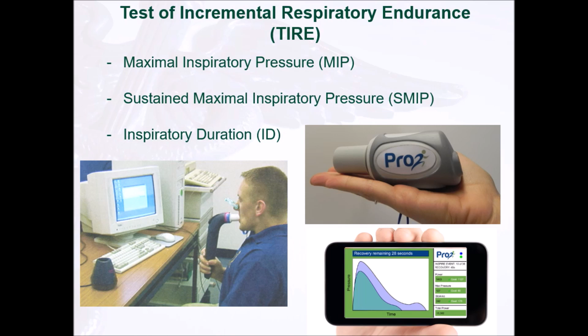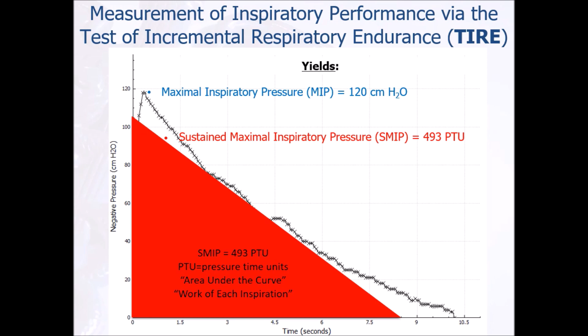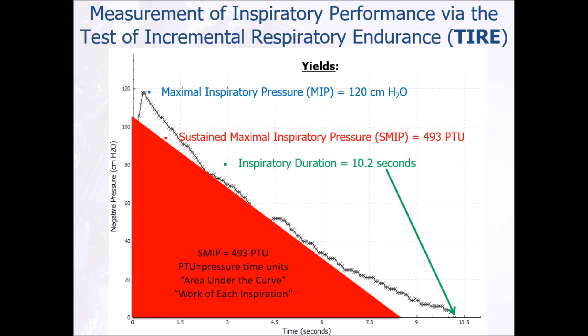The maximal inspiratory pressure, the sustained maximal inspiratory pressure, or the SMIP, and the inspiratory duration, the ID, presented in this particular slide. If we look at this slide, we can see the maximal inspiratory pressure at about 120 centimeters of water, the sustained maximal inspiratory pressure, or the SMIP, which is a unit of measure in pressure time units at about 493. It's the area under the curve reflected during inspiration, and thus it represents or reflects the work of each inspiration. From this same type of device, we can also obtain the inspiratory duration, which we see here at about 10.2 seconds.